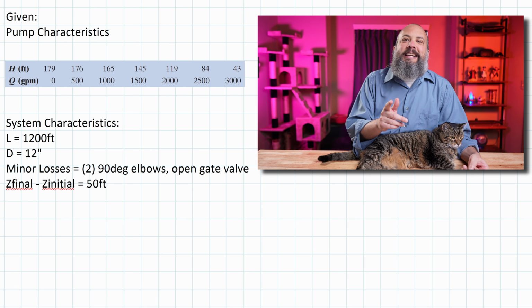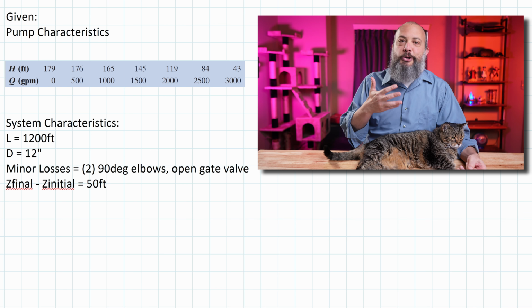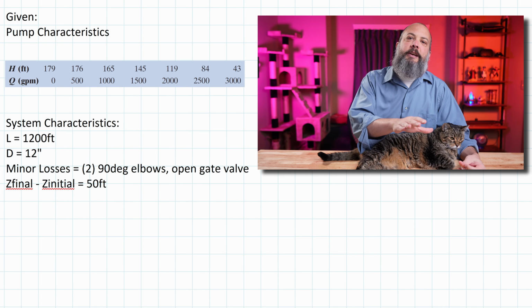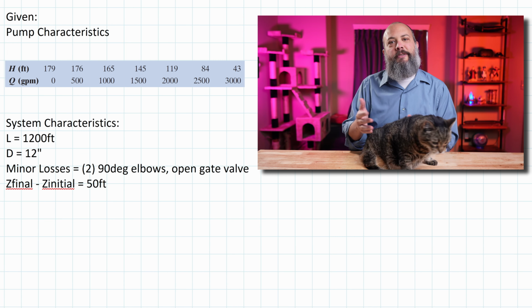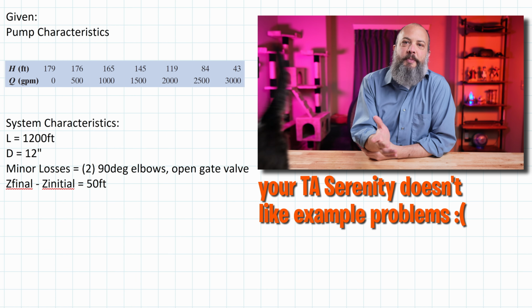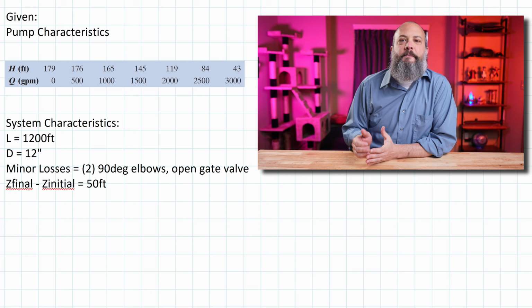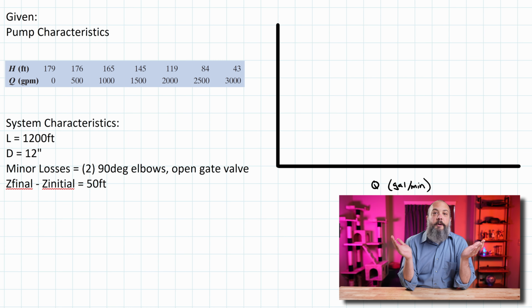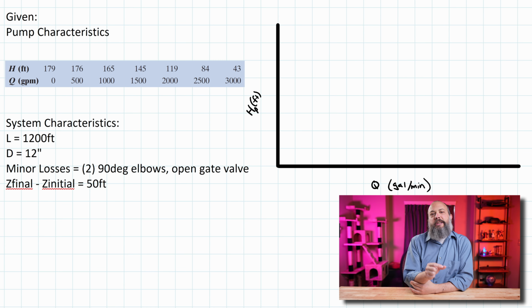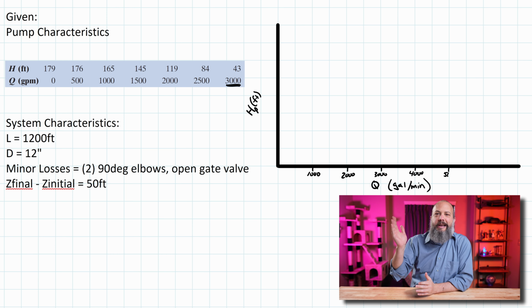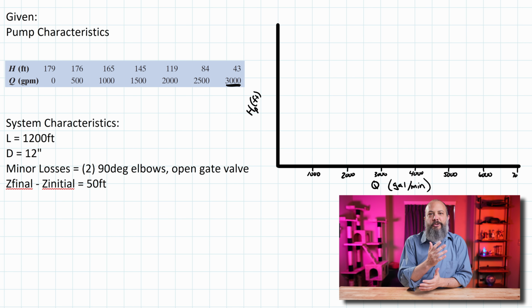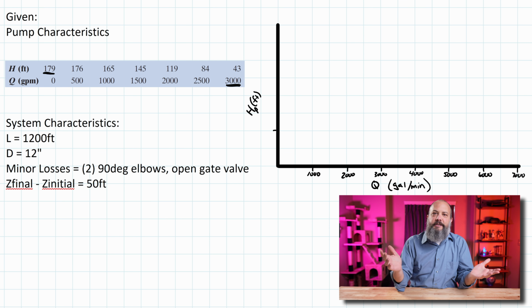So I'm going to work through an example of exactly how you can compare your pump's characteristics against your system curve to help you make the decision as to whether parallel or series pumps would be better for your particular system. This is all going to start off with making a plot of your pump characteristics, put flow rate on the bottom horizontal axis and pump head on the vertical axis. I'm using gallons per minute and feet, but if your system's in different units, that'll be fine too.